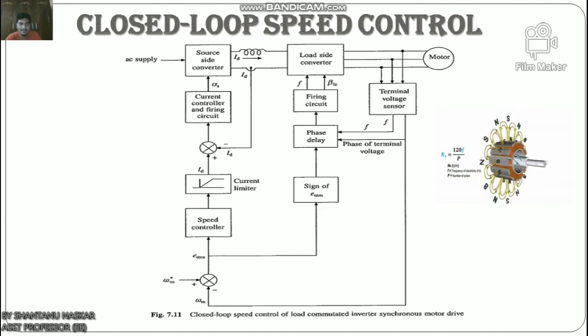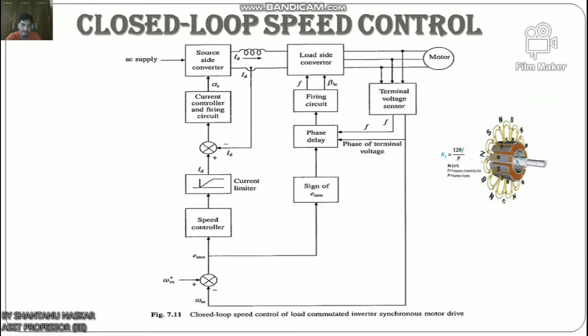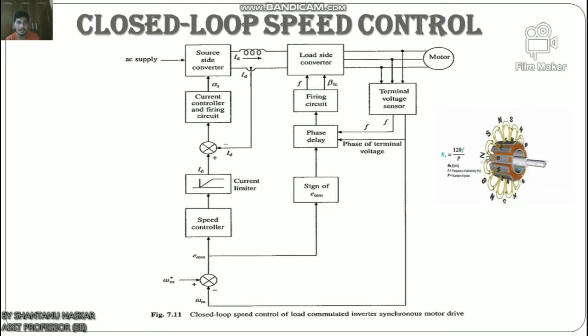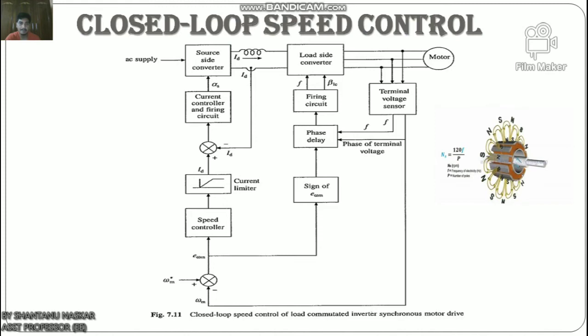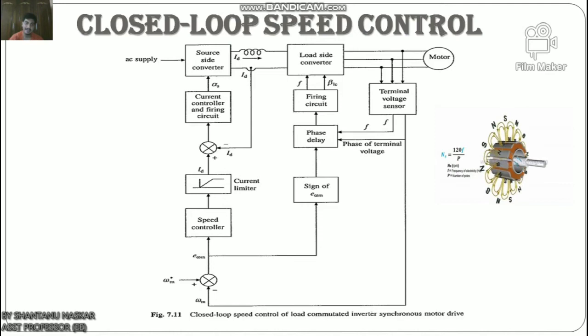When close to the desired speed, the current limiter desaturates and the drive settles at the desired speed with DC link current balancing motor and load torque. Similarly, a reduction in reference speed produces a negative speed error, setting βlc for regenerative braking. When the speed error changes sign, βlc is set for motoring and the drive settles at the desired speed. The key advantages of this drive are: high-efficiency four-quadrant operation with regenerative braking, high power ratings up to 100 MW, and ability to run at high speeds up to 6000 RPM. Prominent applications include high-speed and high-power drives for compressors, blowers, fans, pumps, conveyors, steel rolling mills, mainline traction, ship propulsion, and aircraft test facilities.